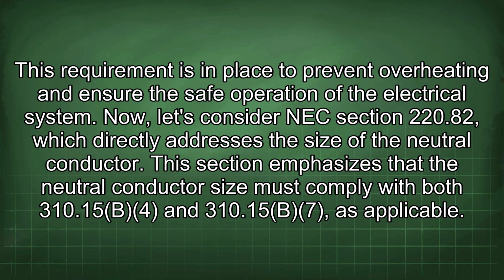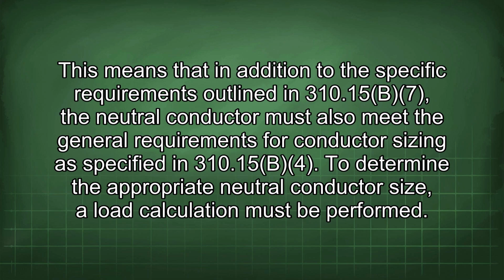Now let's consider NEC section 220.82, which directly addresses the size of the neutral conductor. This section emphasizes that the neutral conductor size must comply with both 310.15(B)(4) and 310.15(B)(7) as applicable. This means that in addition to the specific requirements outlined in 310.15(B)(7), the neutral conductor must also meet the general requirements for conductor sizing as specified in 310.15(B)(4). To determine the appropriate neutral conductor size, a load calculation must be performed.